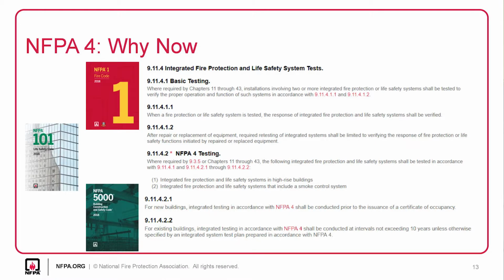That's good for a lot of reasons. One of the biggest is warranties, if you have issues with warranties. Another thing is tracking common issues. So maybe you had to do something in a specific set of rooms after your fire alarms were installed. And then you had to go back into those rooms and do something to the rooms and then reinstall your fire alarm system, so your notification devices. If you start having an issue in a bunch of rooms that you had to do something in, you're going to realize to go check all the rooms that you had to go fix something else in. It's just a good way of keeping track of what common issues are happening within the building during your integrated testing.